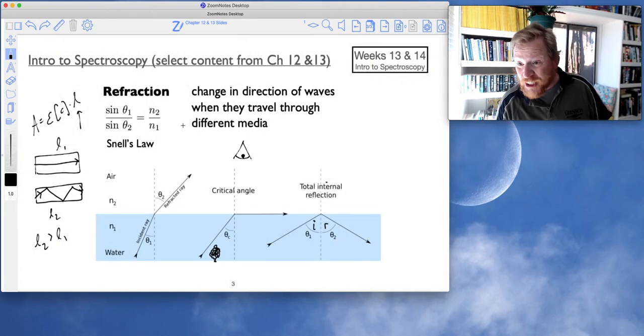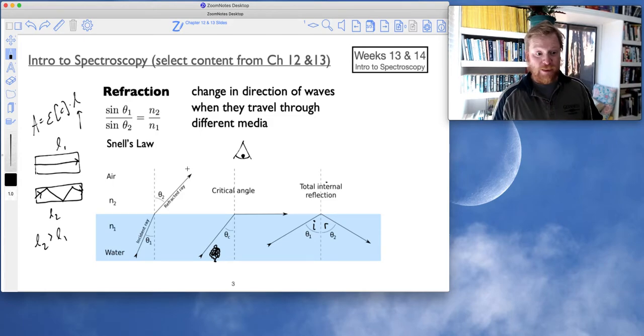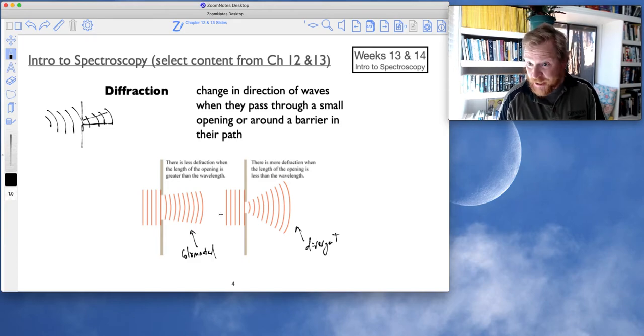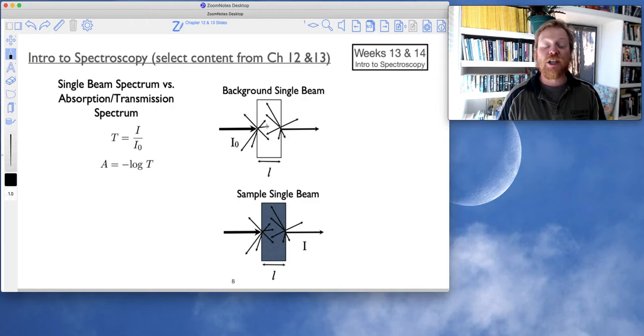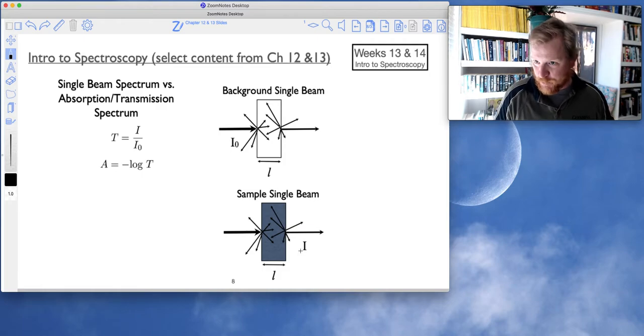We can get refraction if the light is passing through multiple different types of media, which it certainly is in spectroscopy. It passes through the air, and then it passes through your glass cuvette, and then it passes through the liquid in your cuvette, and then on and out through the other side. So all of these processes are important to consider, which is precisely why we take a background spectrum and then a sample spectrum. These are typically referred to as single beam spectra.